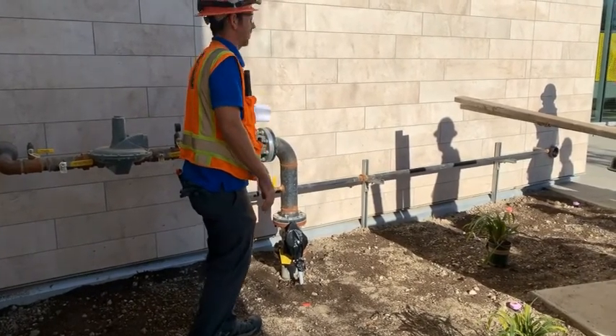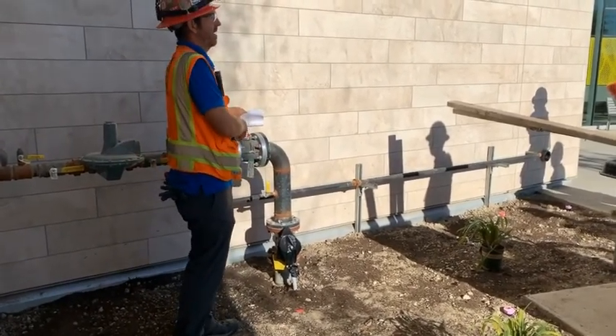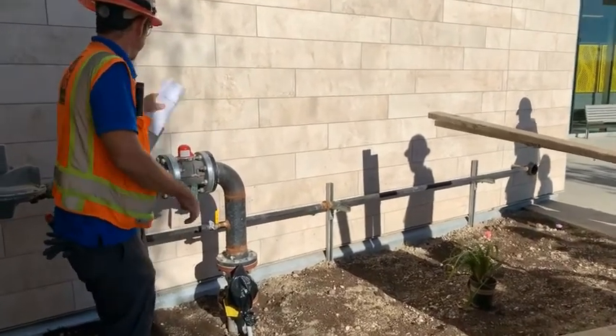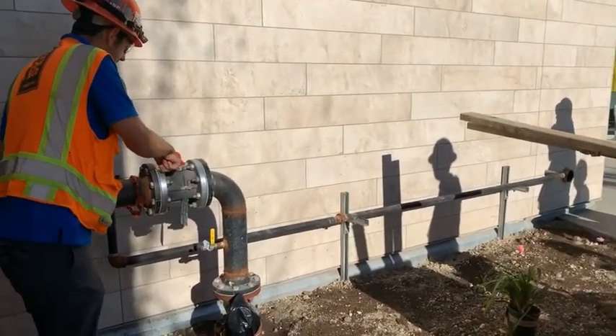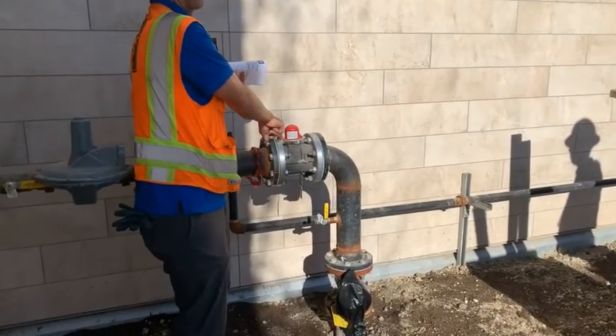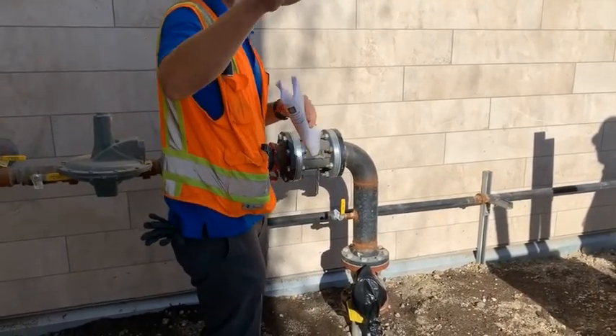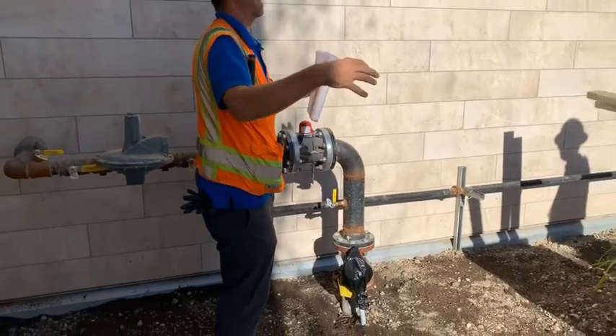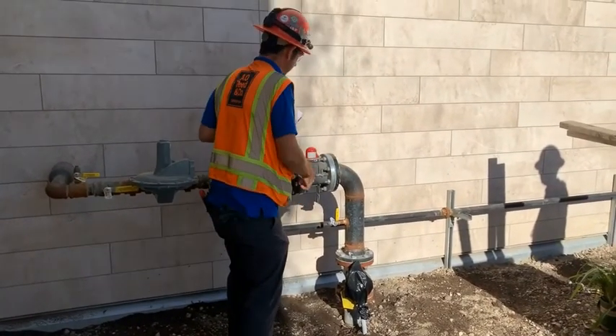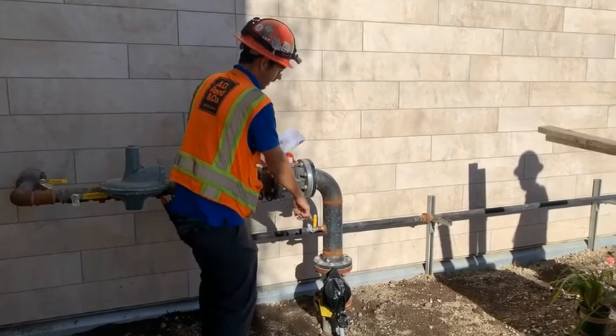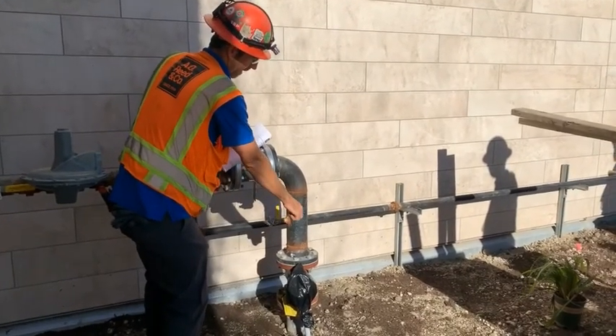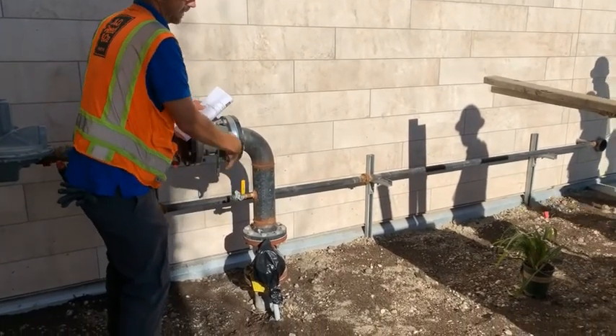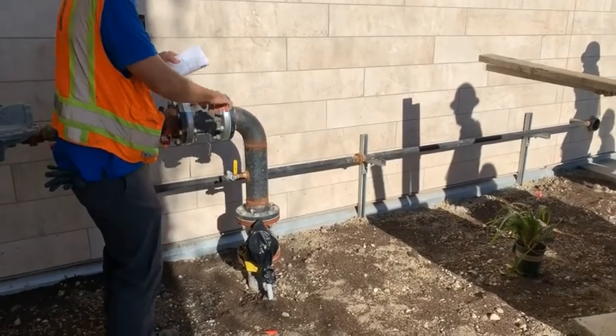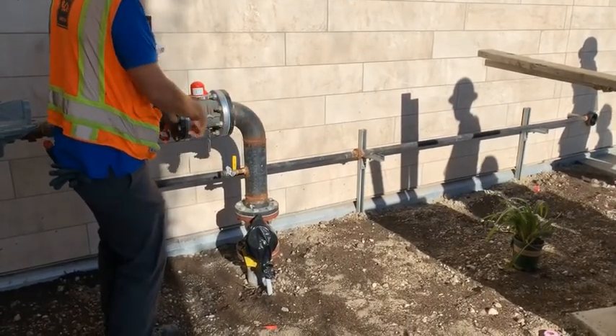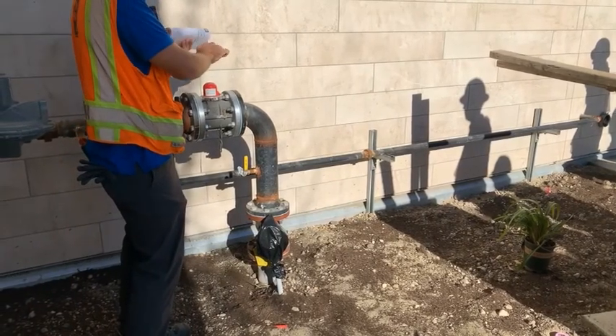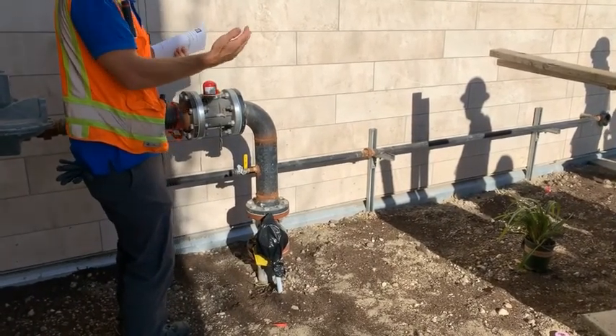We come up, everyone know what this is? Earthquake valve, okay? So the earthquake valve, there's a little sight window right here on the downstream side. Green is good, red would mean it's tripped. It was as easy as some of the landscapers when they were digging in here, when they were hitting the ground, they tripped it. So to reset it, what you need to do is actually turn off the main gas to the building. If it does trip, the gas is already off downstream of it. So you gotta shut off the gas. If there's any pressure built up in it, try to prevent the pressure. When you're venting gas, just be careful. Make sure nobody's smoking.